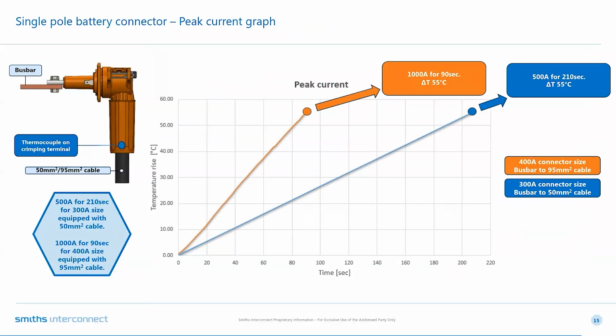Going to the results, the 400 amps connector crimped on a 95 square millimeter cable, that is the orange line in the graph, can carry 1000 amps for 90 seconds, while the 300 amps connector crimped on a 50 square millimeter cable, the blue one in the graph, is able to carry 500 amps for 210 seconds. These results, it's important, as mentioned before, remain stable during all the product life.